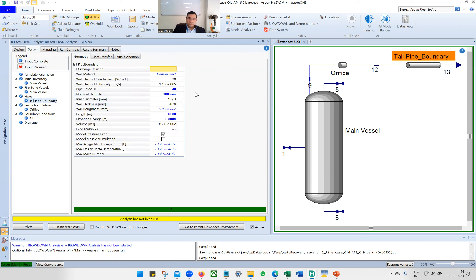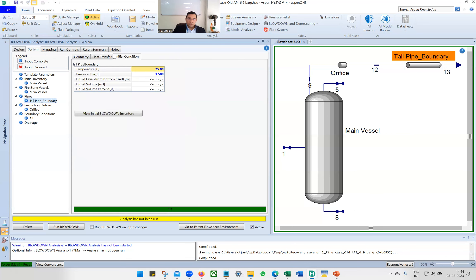For the tailpipe, assume pipe schedule 40, nominal diameter 100 mm — a 4-inch line — with length 10 meters and elevation change zero. For initial conditions, temperature is 25°C, since when the EDPV or BDV is not open, the tailpipe is in equilibrium with ambient conditions.